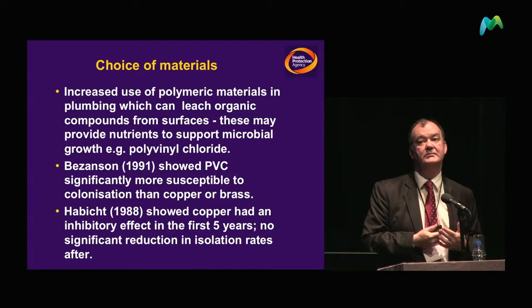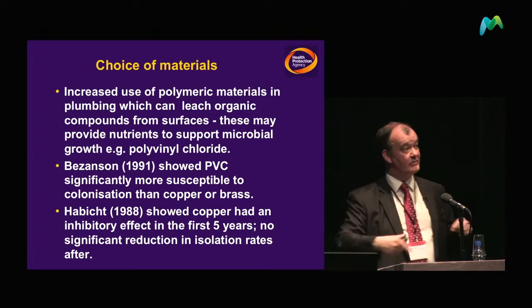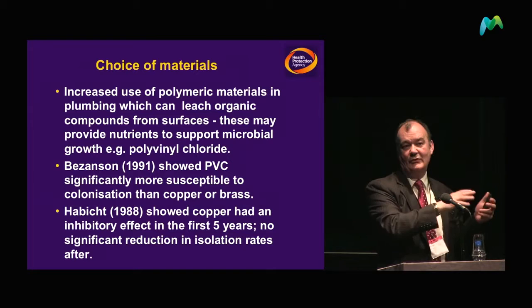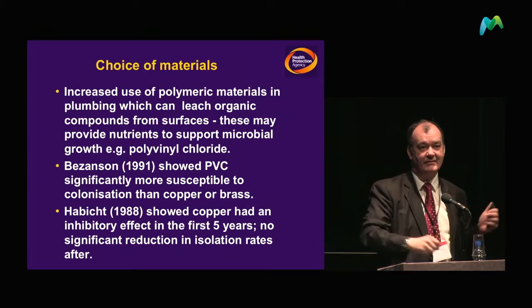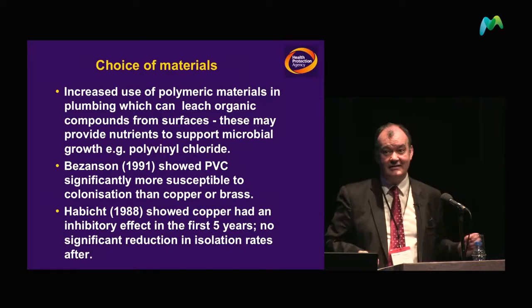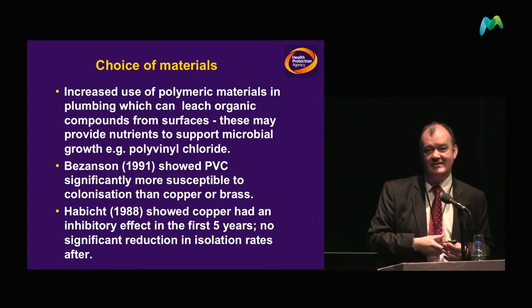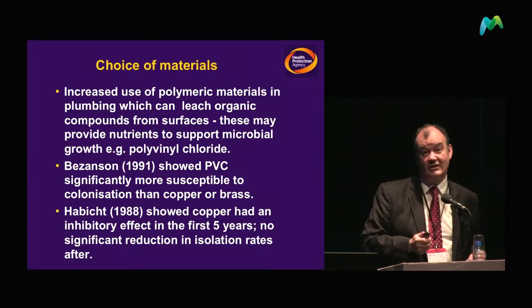New washing machines have only got one inlet pipe, whereas old ones had a red and a blue — hot and cold. What's often happening now is people buying a new washing machine haven't bothered to cap off the existing hot water pipe — they just connect it to the cold water. What they've effectively created is a dead leg or blind end in which Legionella will multiply and grow, and could over time invade the system and cause potential problems.